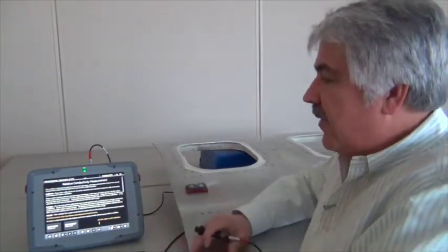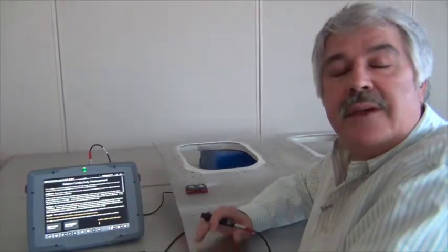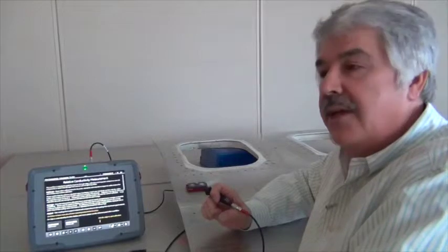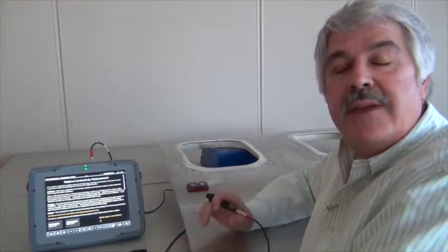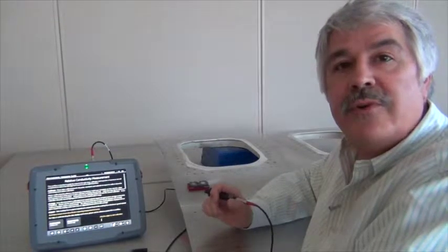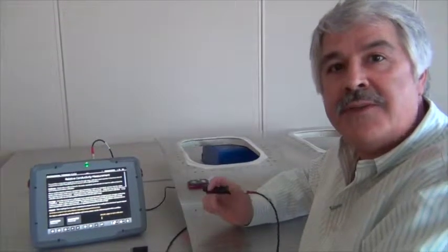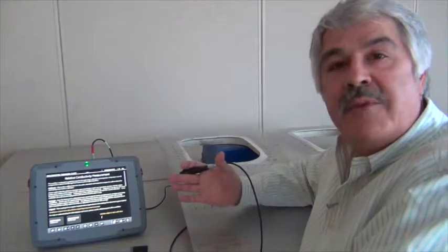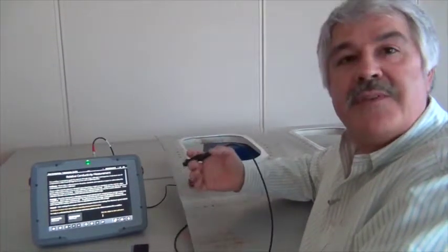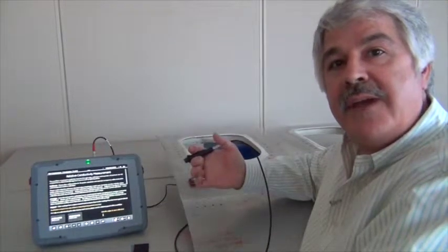So we've really optimized the conductivity feature on the Mentor for comparative or relative conductivity measurements. When properly calibrated, the Mentor provides accuracy similar to or better than the AutoSigma 3000. But we've really optimized this workflow for the major steps in a relative conductivity test.